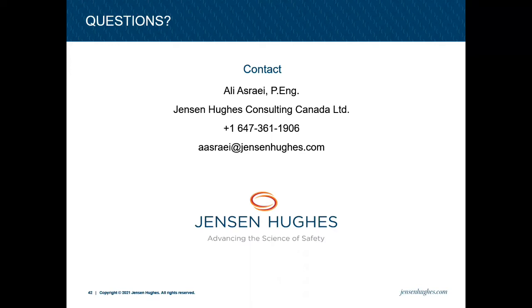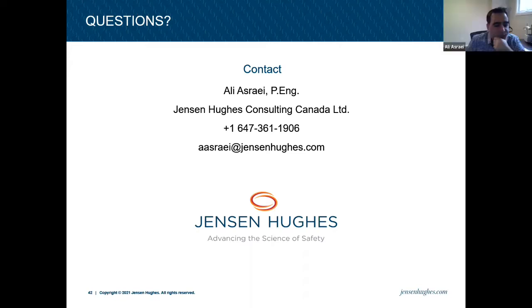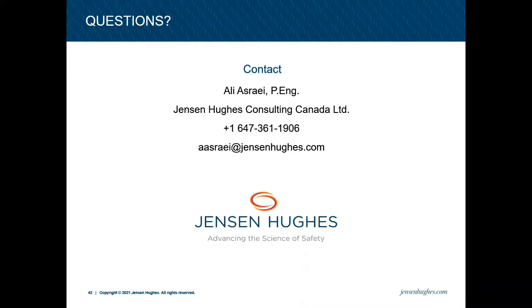Yeah, and Ali, you're aware of this. We chatted about this last week, but we've discussed this with the OFM too: when you're looking at 7.3.1.2 for testing requirements for a smoke control measure, whether it was installed in the 70s or 80s or 90s or 10 years ago, it doesn't matter. There's no cutoff date or anything like that. So 7.3.1.2 would apply to any measure, regardless of when it was installed.